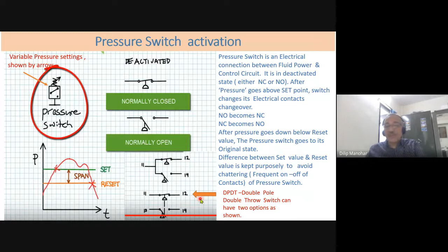This electrical actuation can be used for controlling a motor or a pump. There is a purpose in keeping the difference between the set value and the reset value: to avoid chattering of the pressure switch. If it is very small, the pressure switch tends to chatter a lot. That means it will keep actuating on and off too frequently. To remove that chatter, we keep a small gap between the set point and the reset point. The same thing is shown in the previous slide.